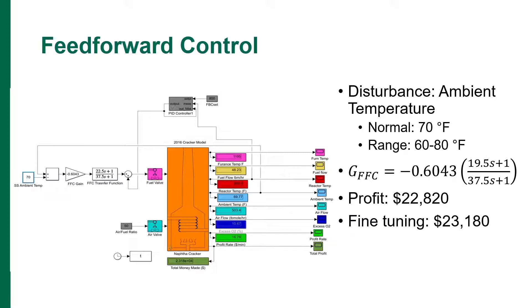To further enhance the performance of the reactor temperature control scheme, we implemented feedforward control in addition to the direct feedback control. From the previous analysis, we discovered that the direct feedback control system alone was ineffective since the primary disturbances, in this case the ambient temperature, was occurring at a frequency which did not allow the system to settle down, namely due to thunderstorms occurring.